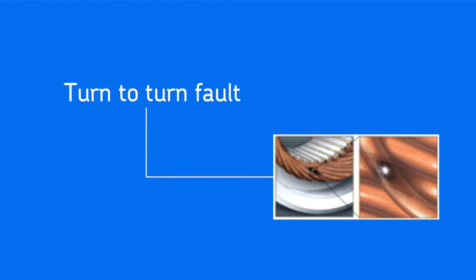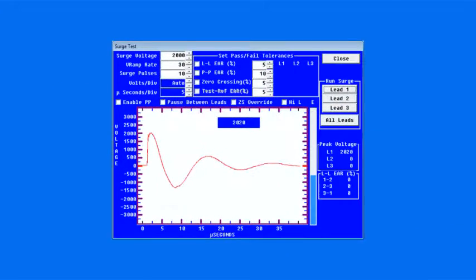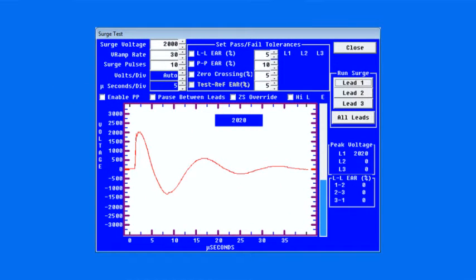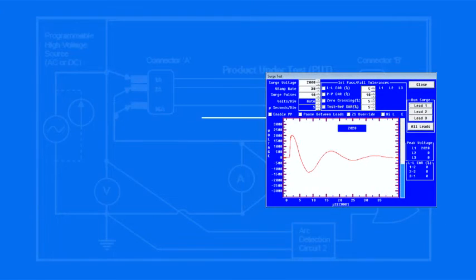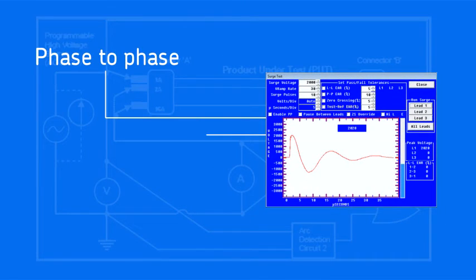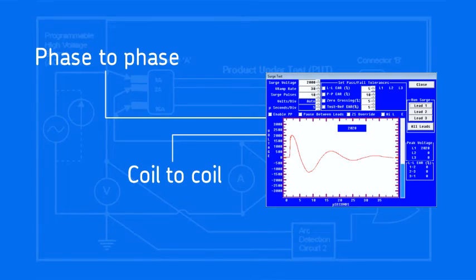The most common insulation failure is between turns of wire that are next to each other in the same coil. This is called a turn-to-turn fault. The surge test is the only test that can reliably test turn-to-turn insulation. The surge test also finds phase-to-phase and coil-to-coil faults in the stator windings.